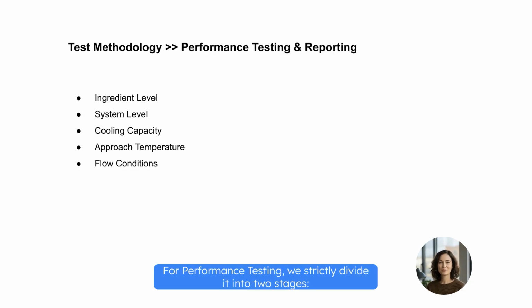For performance testing, we strictly divide it into two stages: ingredient level and system level. You verify the individual pump curves and valve ratings first, before qualifying the full assembly. The real challenge is the industry's lack of standardization.